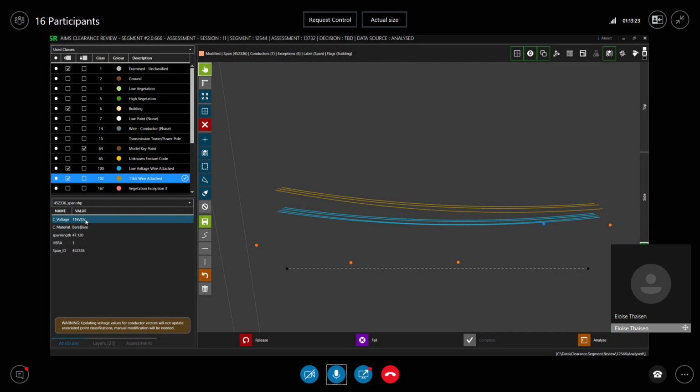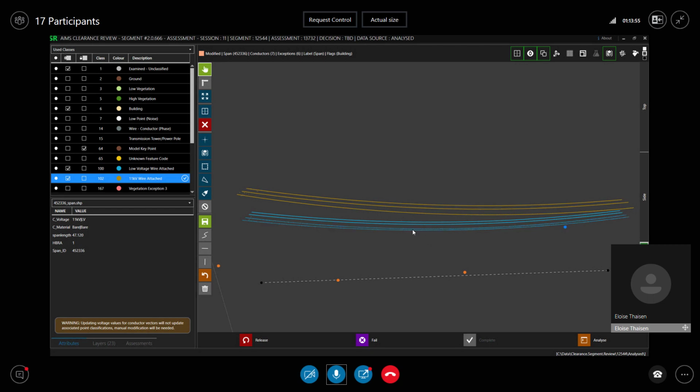So sometimes you might have an additional pipe. Sometimes you might have 3 circuits, sometimes you might have 4 circuits. In this example here, we only have 2 circuits. So the lowest one here gets circuit number 1, and the highest one here is circuit number 2. And if you had another one in front of this, it would be circuit number 3, circuit number 4, and so on. But the rule of thumb is the lowest value here is circuit 1, and that's how we know this is circuit 1.